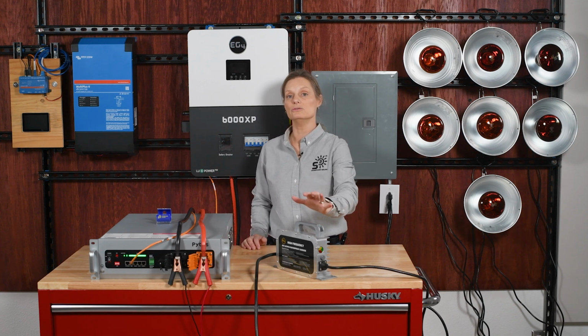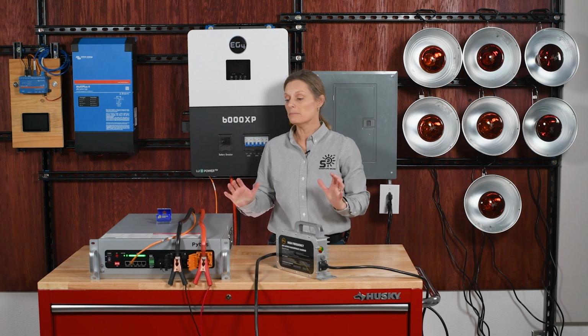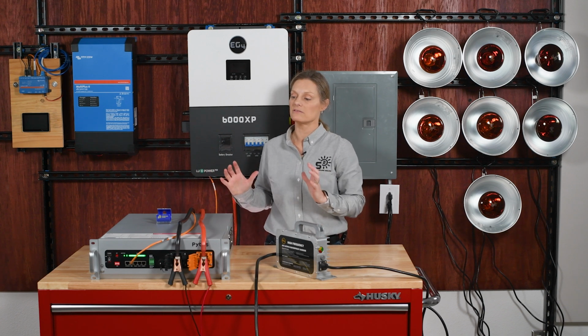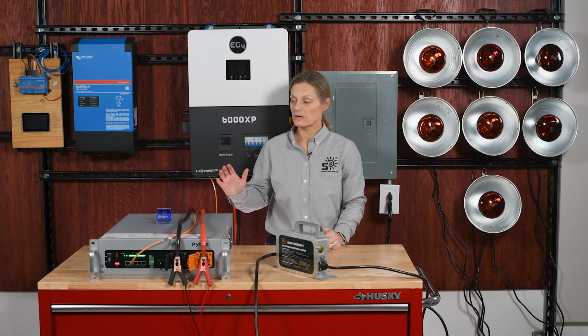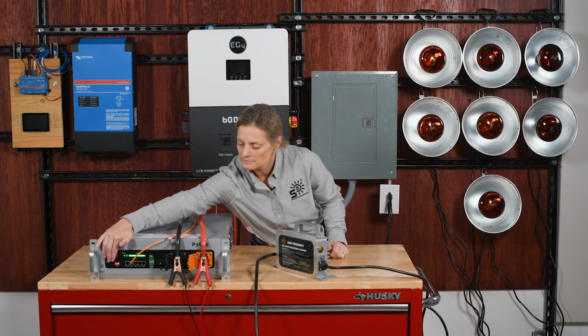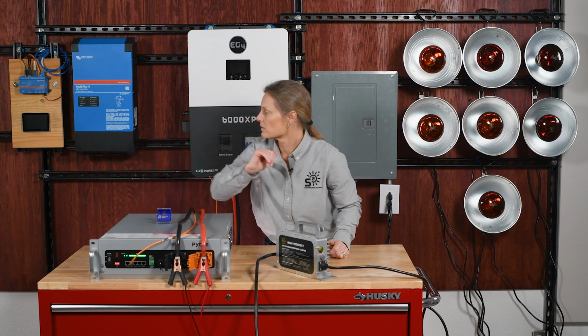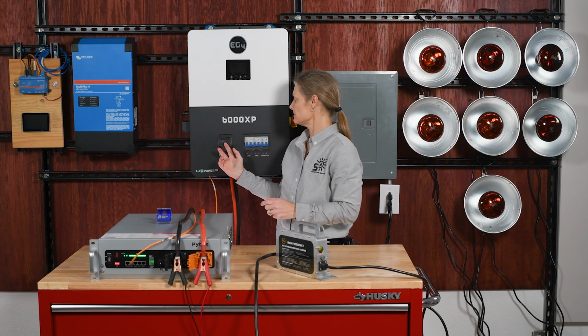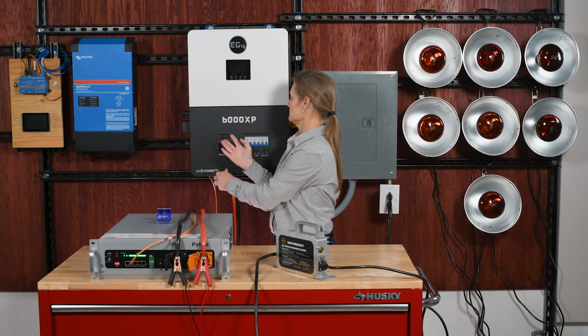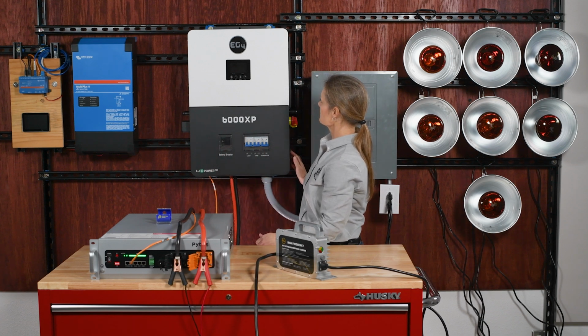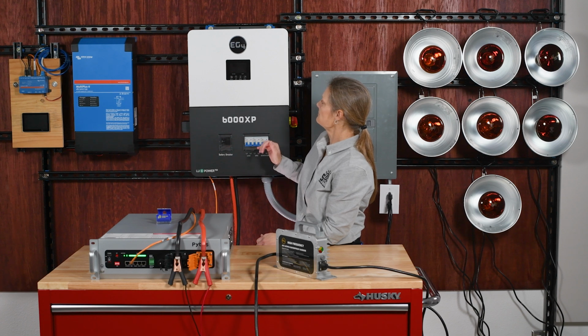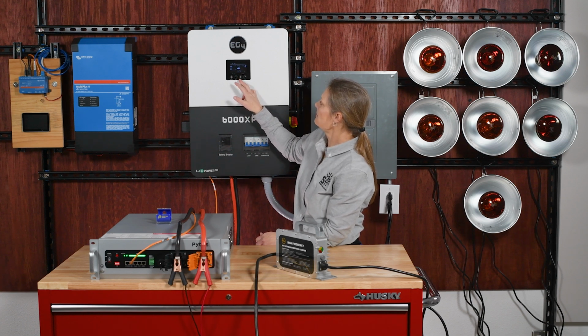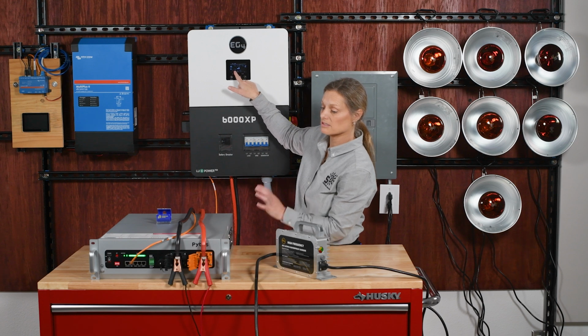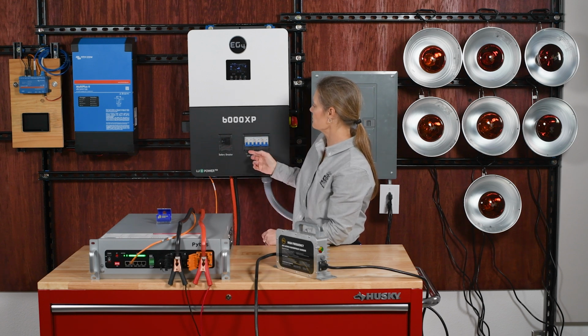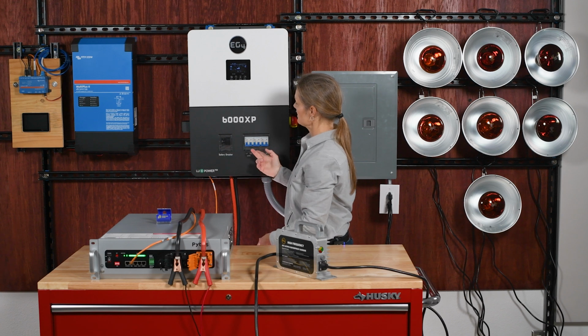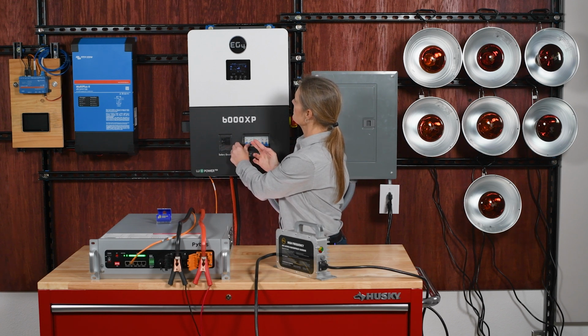We're also making sure to charge this battery all the way up to 100% before we begin to run our test for a discharge. So let's go ahead and turn on the battery. Oh, it's already on. We're gonna go ahead and leave that on. That's right, because we're charging the battery. We'll turn on our battery breaker. Turn on our inverter. And we can see right now our battery's at 94%, so we'll make sure that this charges all the way up to 100%. We'll turn on our EPS output, and then we'll turn on our load.